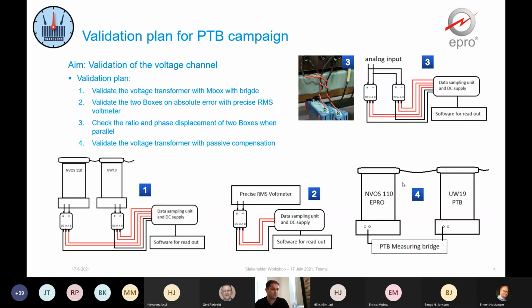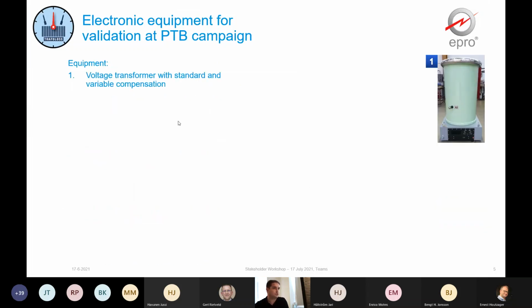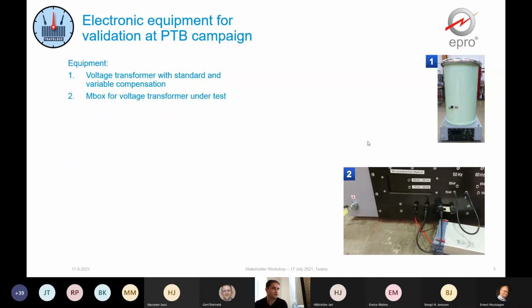And one more thing we could surely do is to validate the voltage transformer itself with the conventional bridge which PTB uses, because the voltage transformer is the foundation here in terms of the small error. And here we can see the overall equipment that we intended to use in the PTB measurement campaign. It consists of the voltage transformer, the test object, up to 100 kV. The second is the box assigned to the test object.